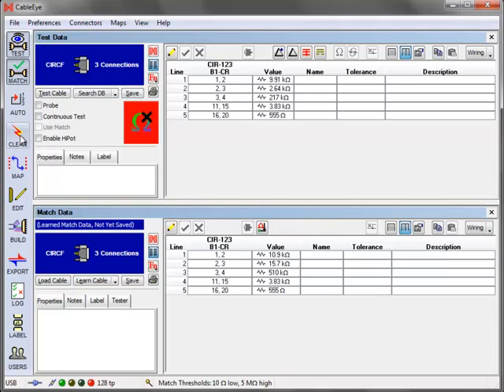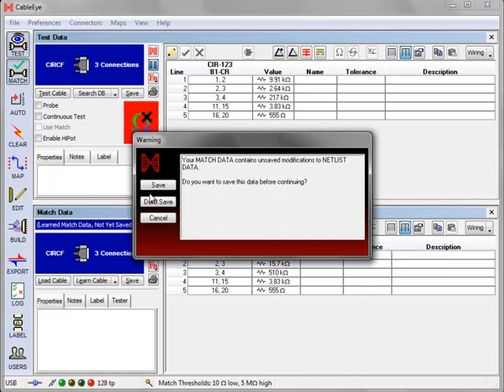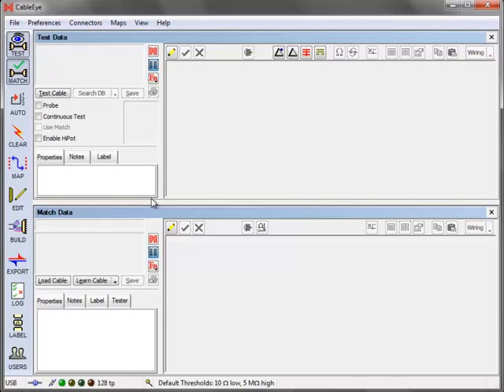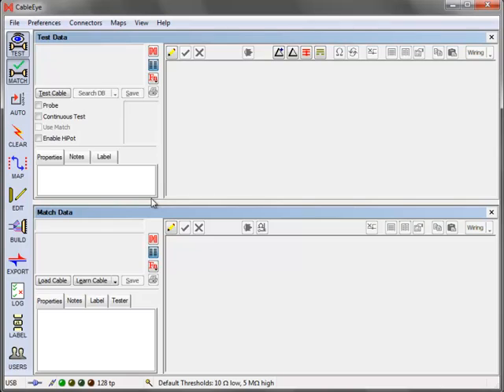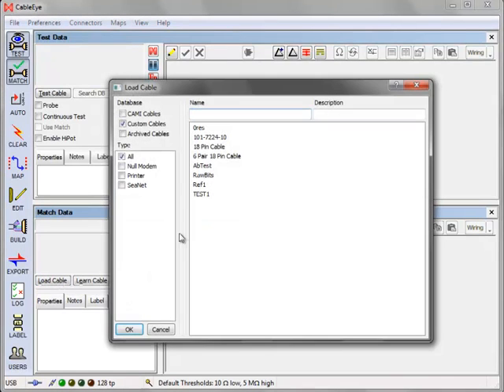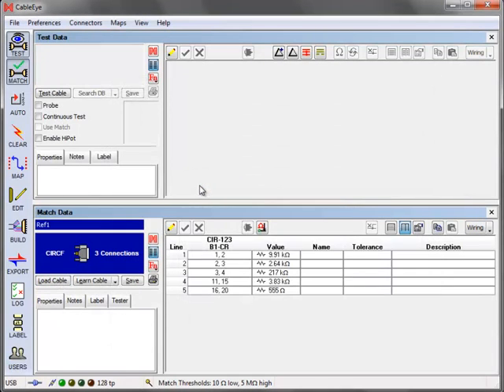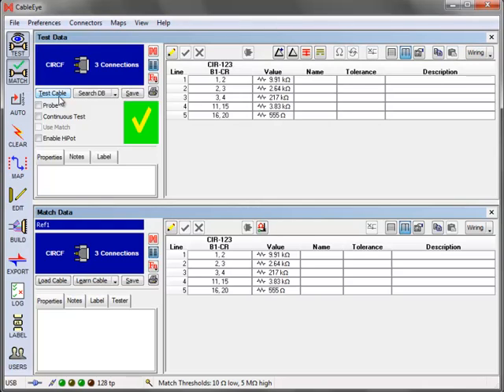To check out the new reference data, first press the clear lightning bolt button. Discard the match data, since we only used it to specify the wiring for the test data acquisition. Now load your new reference cable from the database and test against it. All wiring and resistance values should match and you should get a green check icon in the test data panel.